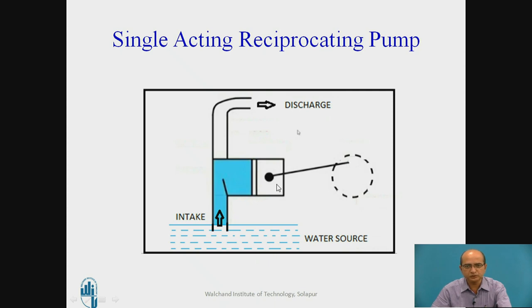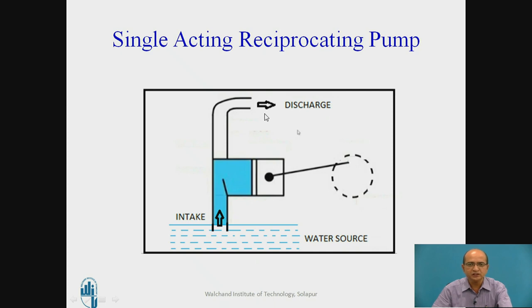When the outermost position is reached by the piston, the connecting rod is at the extreme right-hand side on the circular path — that is the outer dead center. The inner dead center is at the extreme left-hand position. After that, the piston moves inward toward the inner dead center. Due to the pressure acting on the water, the inlet valve closes automatically, and the delivery valve opens. The water goes to the delivery pipe and is collected in the storage tank.